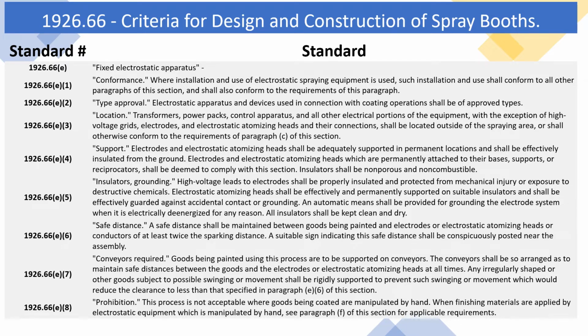1926.66 E2. Type approval. Electrostatic apparatus and devices used in connection with coating operations shall be of approved types. 1926.66 E3. Location. Transformers, power packs, control apparatus, and all other electrical portions of the equipment, with the exception of high-voltage grids, electrodes, and electrostatic atomizing heads and their connections, shall be located outside of the spraying area, or shall otherwise conform to the requirements of paragraph C of this section.